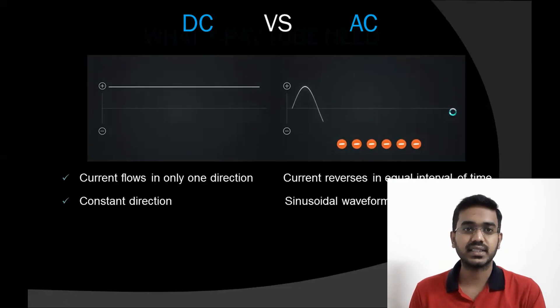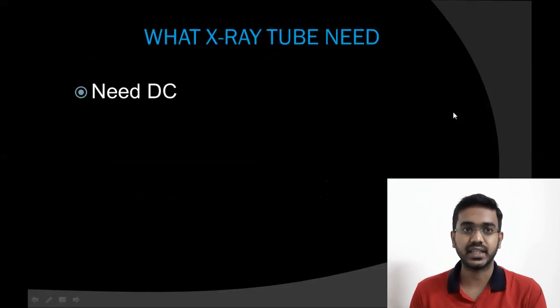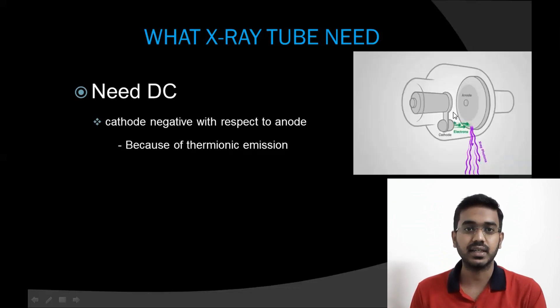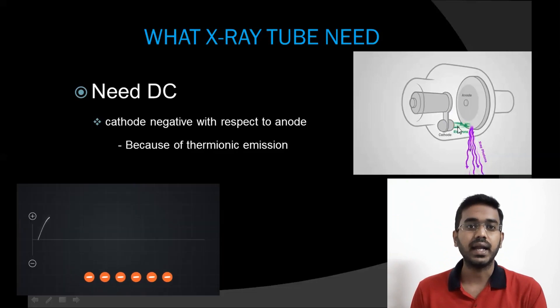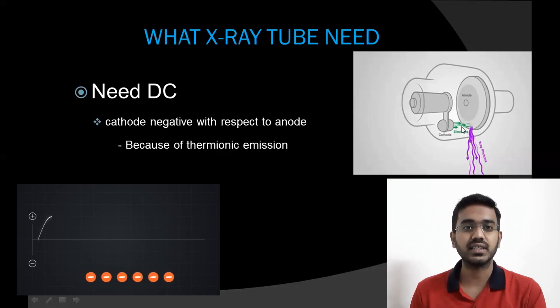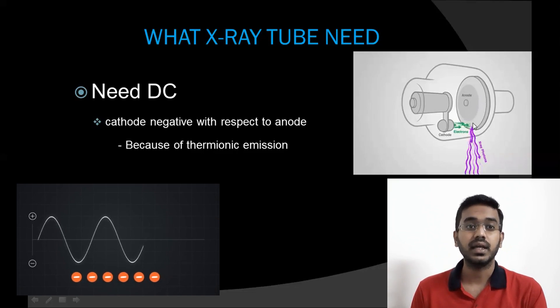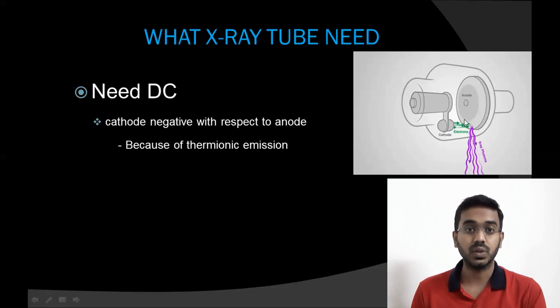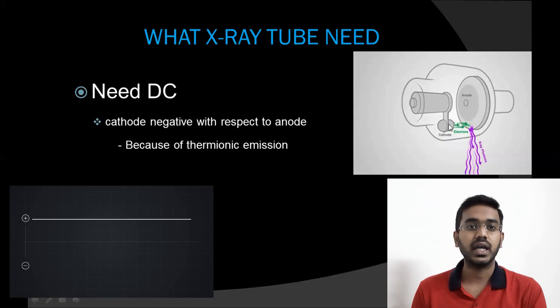Now let's discuss why we need direct current for the X-ray tube. If we give alternating current to the X-ray tube, during the first half of the cycle, the electron comes from the cathode and hits the target. Since AC is alternating in nature, the current reverses during the second half of the cycle. Here, the electron may flow from the target and hit the cathode, which will damage the cathode. So we need a constant current that flows in only one direction — from cathode to anode. Hence, we need direct current.